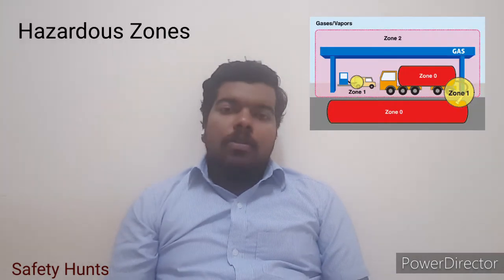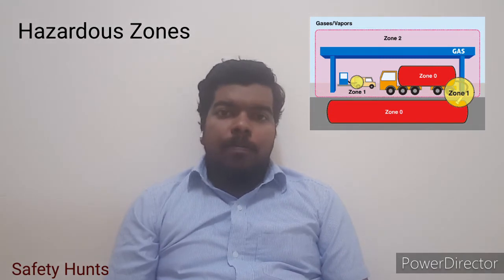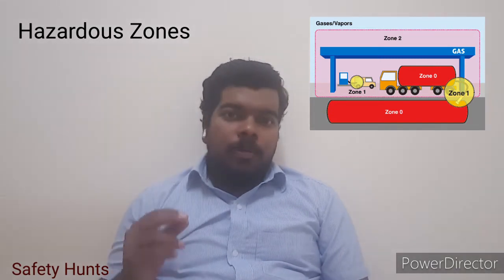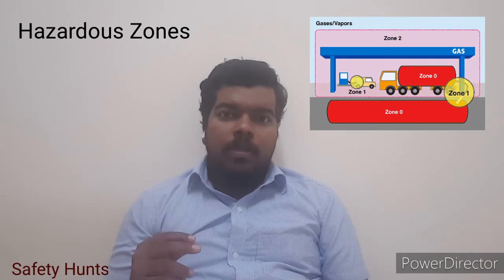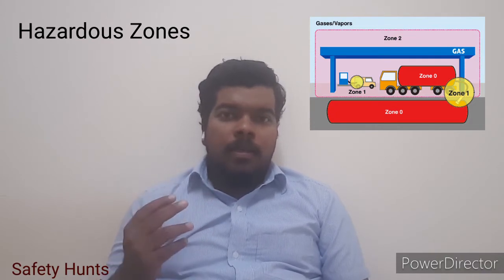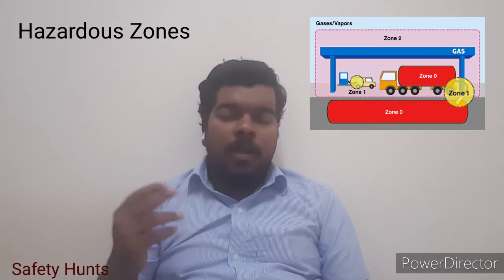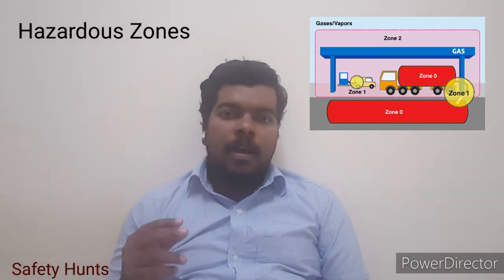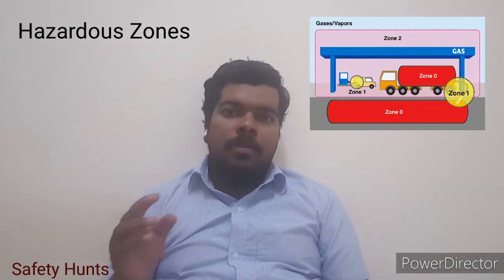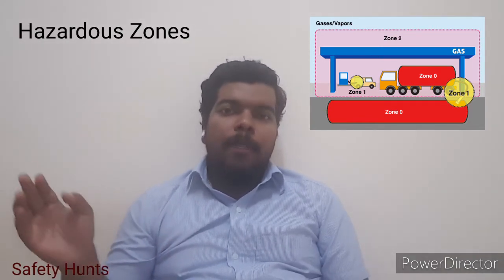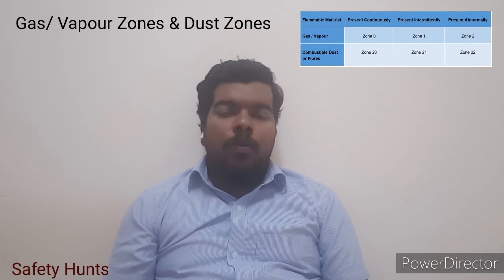Hazardous areas are classified into zones. The basic concept behind the zone is that the duration and frequencies of hazardous substance — the flammable and explosive substance present in air — depends on how we classify the zones. Zones are classified into two major categories: gas and vapour zones, and dust zones.